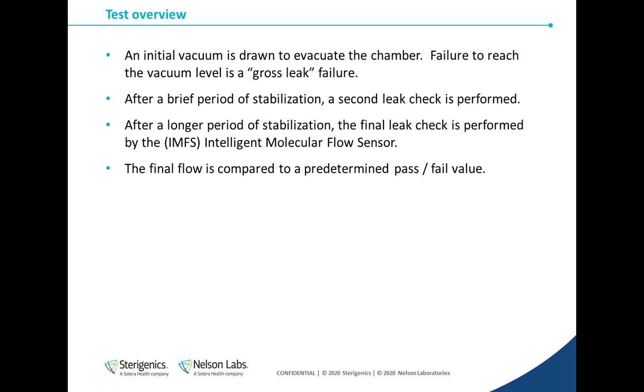How does a test method work? To begin with, the instrument draws a rapid vacuum as part of the gross leak check. This is 2.3 seconds in our vial method example. If the vacuum reaches stabilization before the time is up, then the test will progress to the next step. If the stabilization isn't reached, then the test will terminate. The next leak check is the large leak check. Both leak checks are mainly designed to protect the instrument from moisture contamination. And then this is followed by a long stabilization phase.